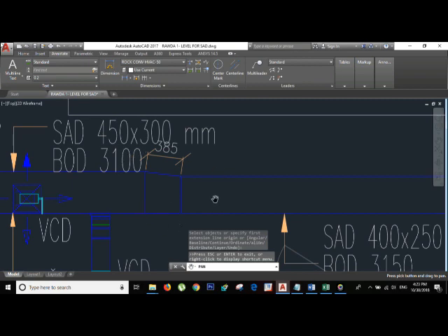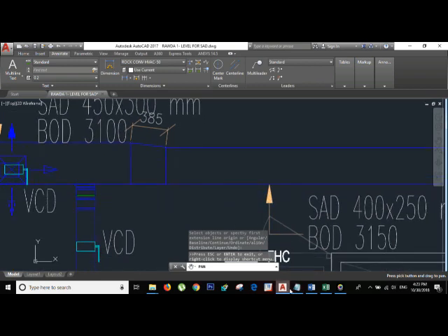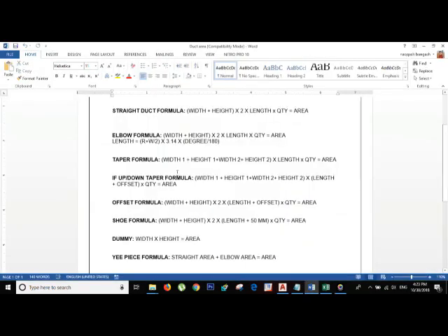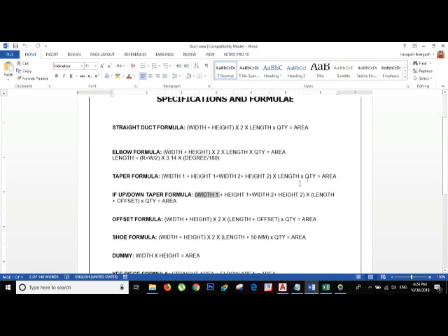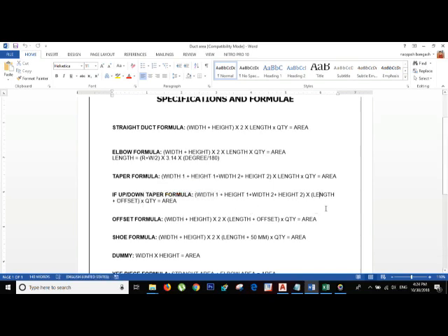For this, the formula is the same — Height 1 plus Width 1, add all widths and heights, multiply by length — but for the length you need the reducer length plus the offset. If it's offset down, how much is it down; if offset up, how much is it up. For example, if the reducer length is 400 and the downward offset is 220 mm, then 400 plus 220 gives you the total length. The rest of the formula is the same.